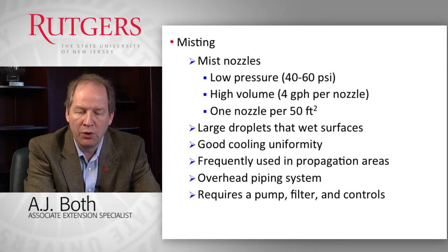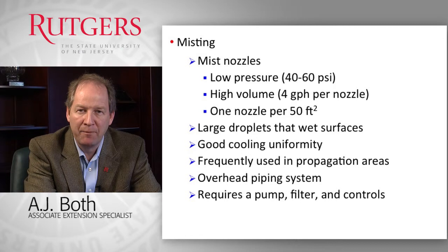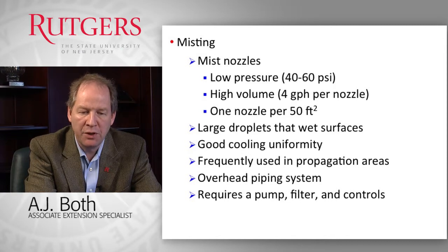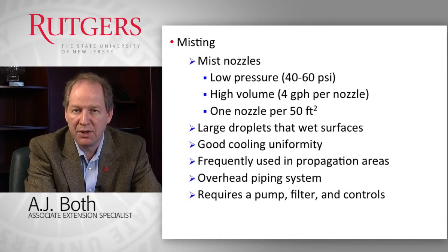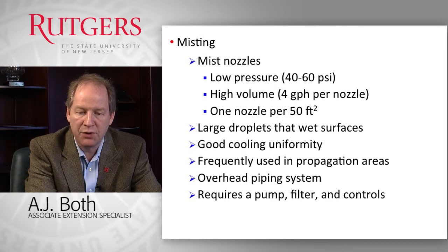Misting systems provide pretty good cooling uniformity — perhaps better than the evaporative cooling pad — because we can put those nozzles throughout the greenhouse environment. In the pad and fan system, the pad is installed on one side of the greenhouse, and although the cooling efficiency is good, as air moves through the greenhouse it picks up heat energy and heats up, creating some non-uniformity of cooling distribution. We typically deliver water through an overhead piping system, which requires a pump, filters to prevent clogging, and controls to operate the system.